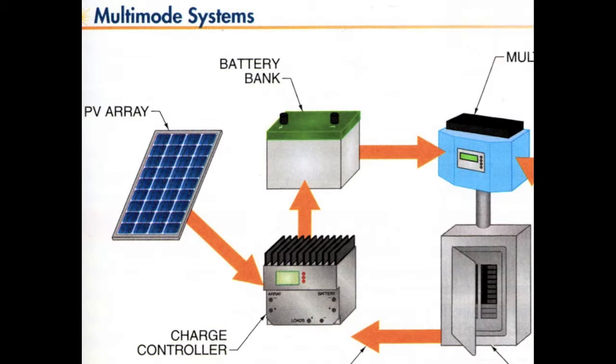During the off chance that the grid does go down, the inverter senses it, disconnects from the grid, and then uses the battery bank to supply the sub panel, which is connected to your system critical loads, to continue to feed them power. A computer, a refrigerator, water pumps, whatever they may be, they will continue to have that power from the battery bank. And at this point, your system is operating in standalone mode.